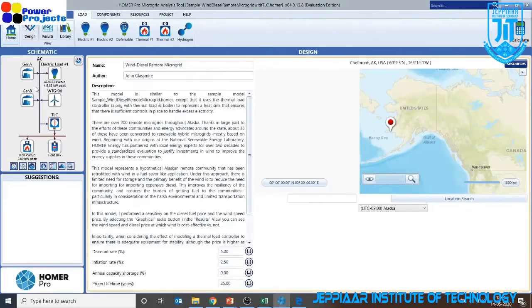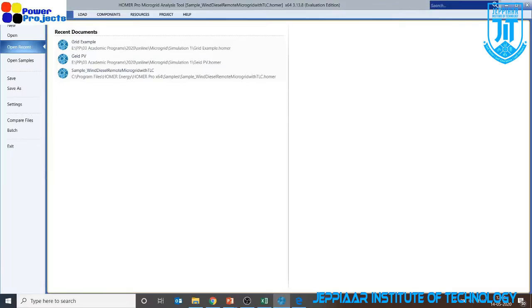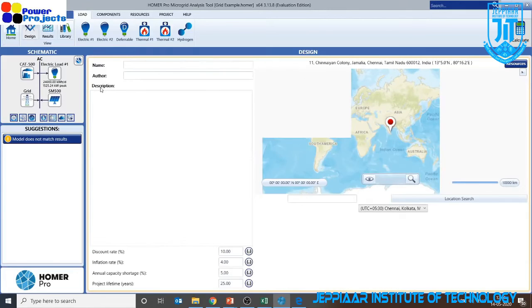Yeah, here probably let me open my file itself. Grid example which I have drawn. So here, countries like India are based on a fixed grid demand. That means you should not go beyond it. Say for example, if 1000 kilowatt is the demand, the industry has to ensure that the demand is not more than 1000 kilowatt. If you are drawing more than 1000 kilowatt, then you have a penalty for that.